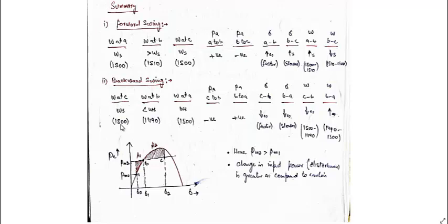Omega at C is again synchronous speed. Omega at B is less than synchronous speed; at backward swing, the speed will be less, let us say it is 1490 rpm. Omega at A is again equal to 1500 rpm. Accelerating power from C to B is negative. Accelerating power from B to A is positive. Delta from C to B is decreasing, but it decreases faster because we have a good amount of decelerating power available. Delta from B to A decreases, but slower.